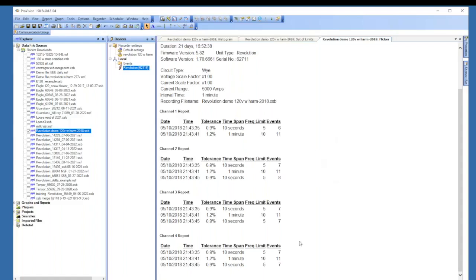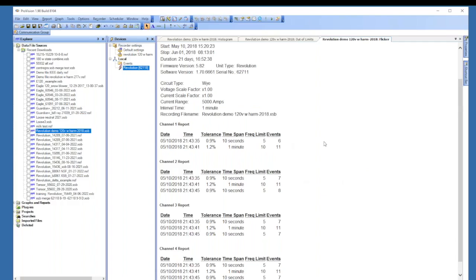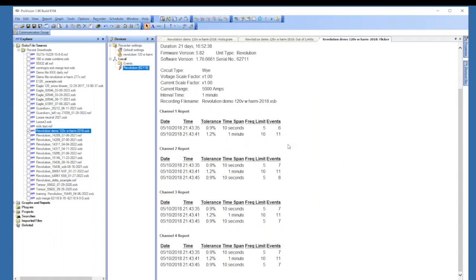If you recorded neutral, you may see a lot of chatter on the channel 4 if you have that on neutral for the flicker report, and that's kind of normal. You really don't worry too much about flicker on neutral. Since it's a percentage, neutral is usually very low voltage, so 0.4 just changing by 0.9% could happen quite a bit. So if you do see small amounts there, then your voltage is pretty stable. But any events, and you'll see there is a limit, and then if that limit is exceeded, then it will create an entry in this report. And it just tells you at what time we had a 0.9% tolerance over a 10-second period, and we had 6 times it broke out of that.